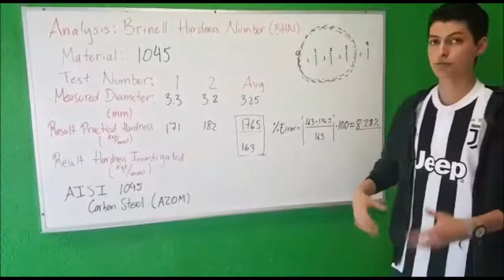So we have 3.3 and 3.2. We got an average of that, and then we searched in the tables for the Brinell hardness number in kilogram force over square millimeter, and we got this average. Then we investigated in the American Iron and Steel Institute for the 1045 Brinell hardness number, and we got 163. We calculated a percentage of error, and we got 8.28, which is pretty close, given that it's lower than the 10% that is normally accepted.